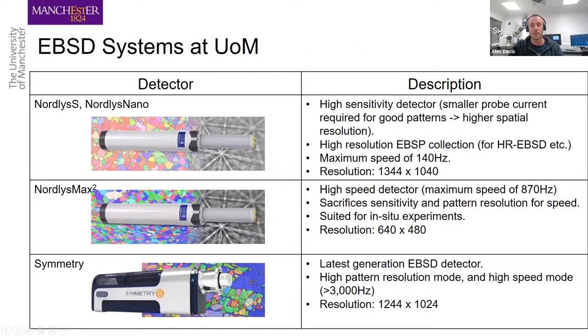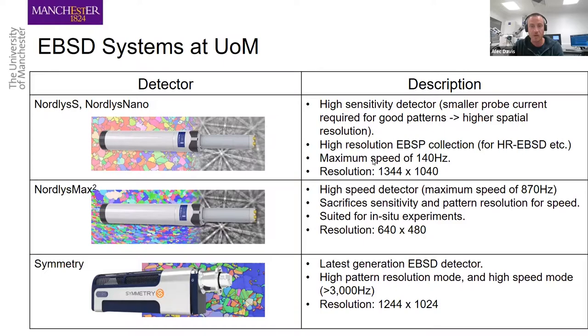Here is a list of all the equipment we use at the University of Manchester. All of our equipment is produced by Oxford Instruments, so a lot of the software-based work today will be based around their software and systems. We have three different sets of detectors: the older CCD cameras — the NordlysS and NordlysNano — on microscopes such as the Sirion and Quanta 650. These are high sensitivity detectors with good spatial resolution, a maximum speed of 140 Hz, and a resolution of 1344 by 1040.